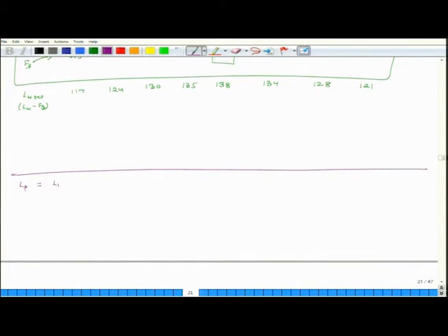LP is equal to LW plus 10 log 10 of 4 over R plus Q by 4 pi R square plus 0.1. Now, we know that LW is 142 decibels, we have calculated it.